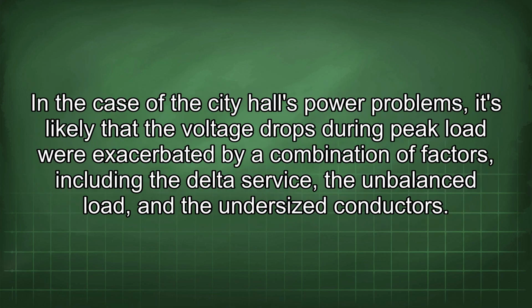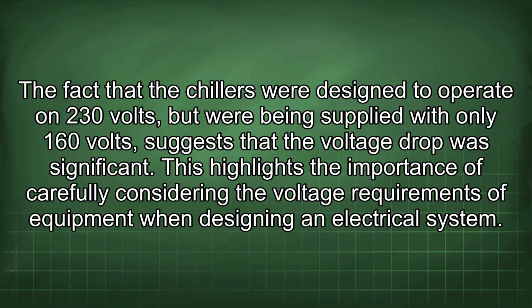In the case of the city hall's power problems, it's likely that the voltage drops during peak load were exacerbated by a combination of factors, including the delta service, the unbalanced load, and the undersized conductors. The fact that the chillers were designed to operate on 230 volts, but were being supplied with only 160 volts, suggests that the voltage drop was significant. This highlights the importance of carefully considering the voltage requirements of equipment when designing an electrical system.